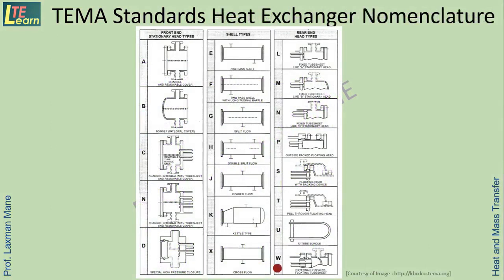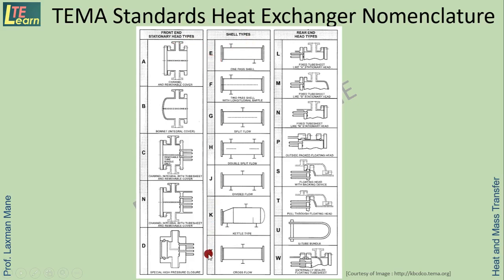TEMA standards provide heat exchanger nomenclature. Heat exchangers are classified into three main types: front end stationary head types, shell types, and rear end head types. Front end stationary head types are classified with letters A to D. Shell types are classified with letter notations E to X, and rear end head types are classified with letters L to W.